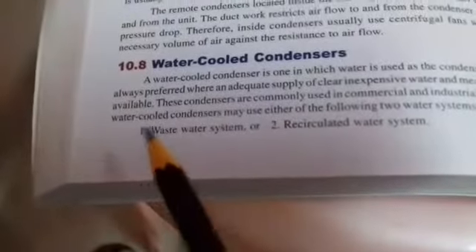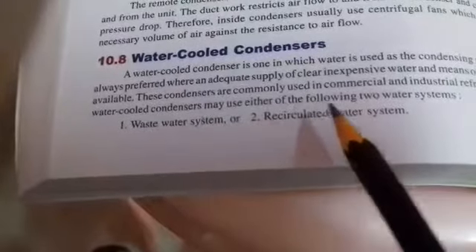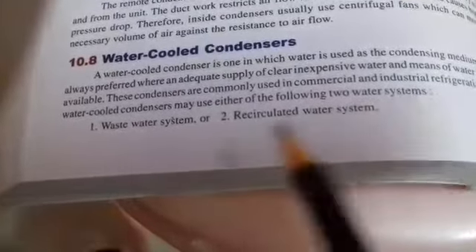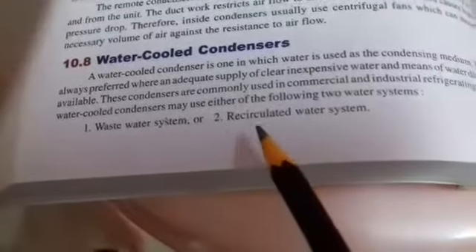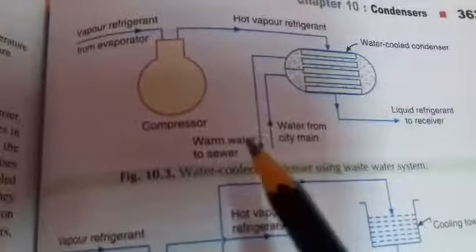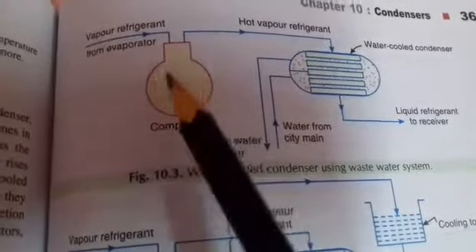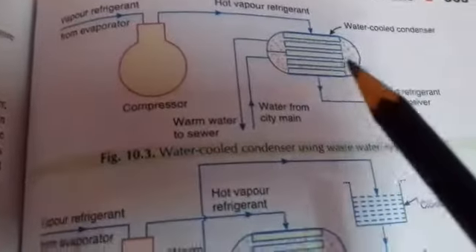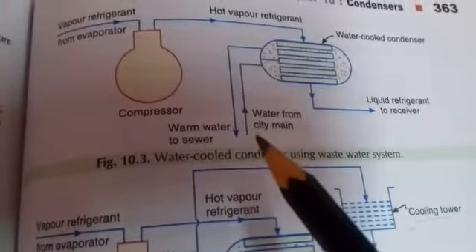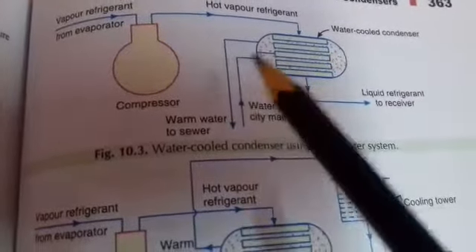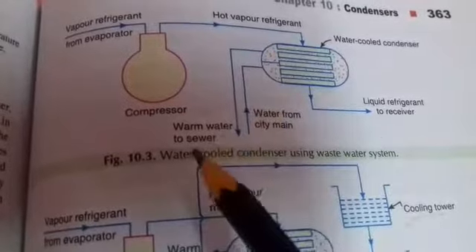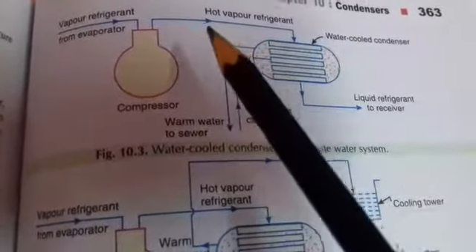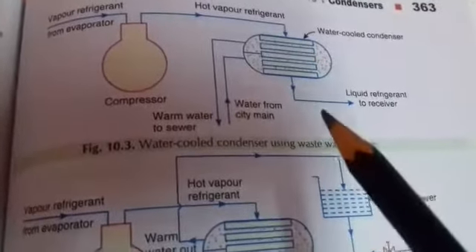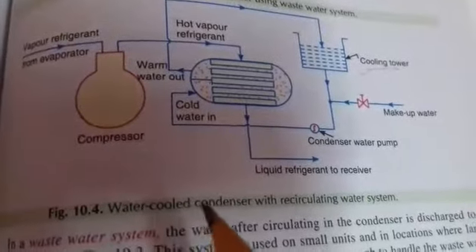The water cooled condensers may be either of the following two water system. First, wastewater system. Now there is a sketch also for the wastewater system, vapor refrigerant going from compressor to condenser. In condenser, the water supply, water from city main, it comes in, and then warm water is going back to sewer, but it is wastewater, and the refrigerant is being condensed over here, and liquid refrigerant goes to receiver.